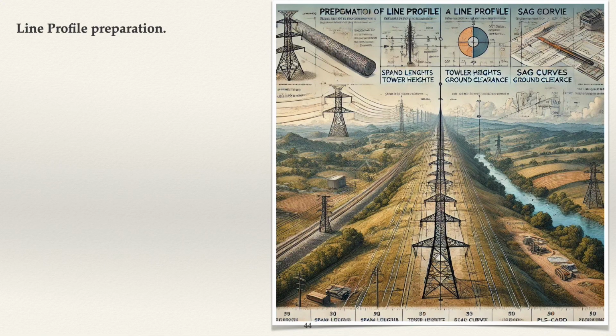Before finalizing, the line profile and tower spotting are reviewed and verified by the design team, consultant engineers, and the client. This process includes cross-checking alignment, clearances, and terrain profiles, incorporating feedback from stakeholders or adjusting for new constraints, e.g., permissions, unforeseen obstacles. Ensuring compliance with standards such as IS, Indian Standards, IEC, International Electrotechnical Commission, or other local guidelines. Once agreed upon by the CE and the client, the finalized profile is submitted for their approval by the contractor.